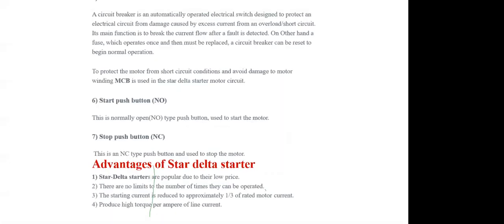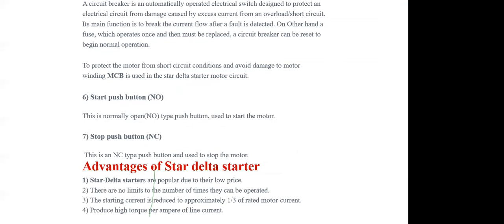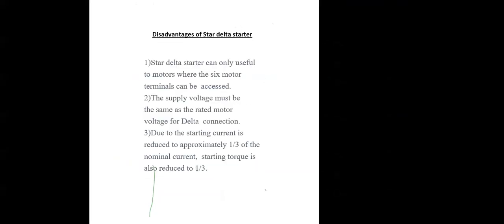We have come to know what the components of a star delta starter are. The advantages: star delta starters are popular due to their low price, and there is less limitation on the number of starts. It is very popular because the starting current is reduced to approximately 1/3 of the rated motor current, and it produces high torque per ampere of line current. This is the ultimate result, the starting current is reduced.